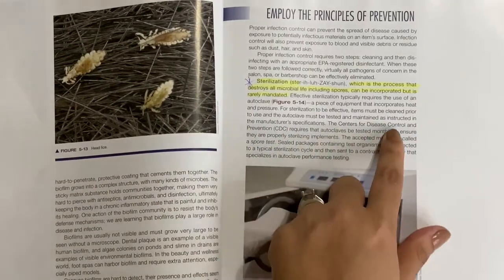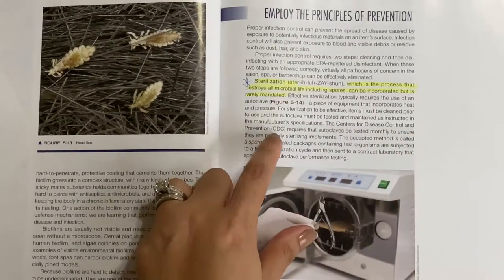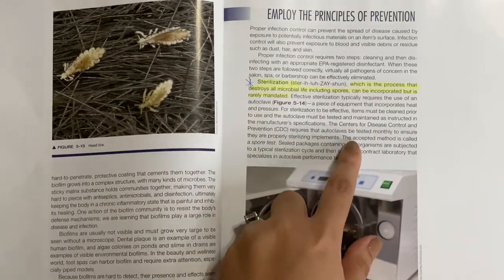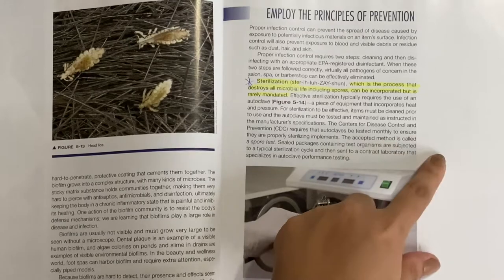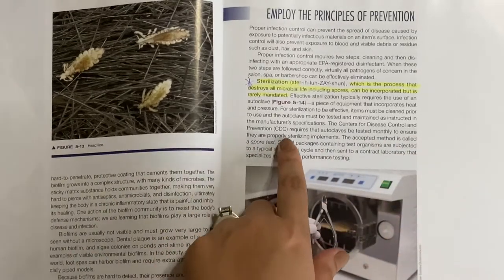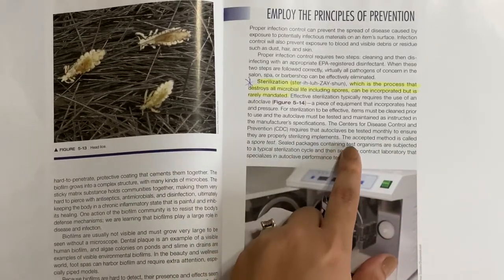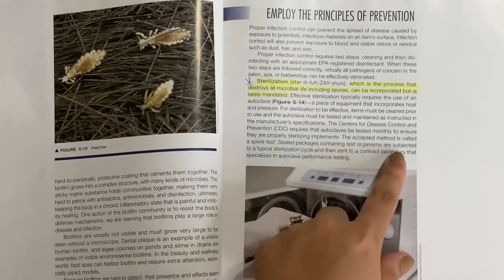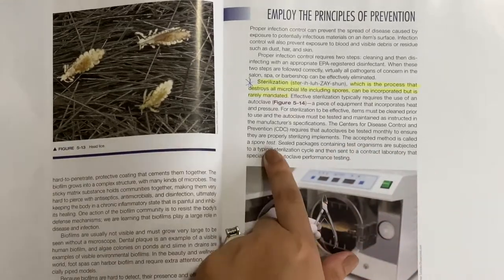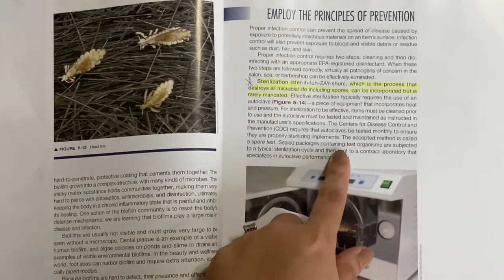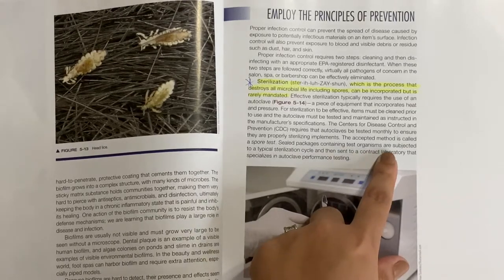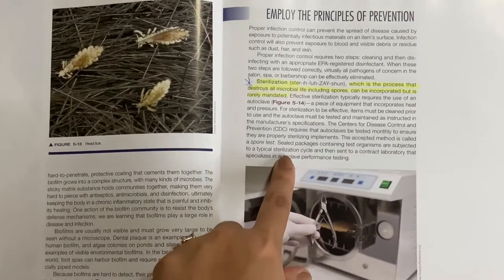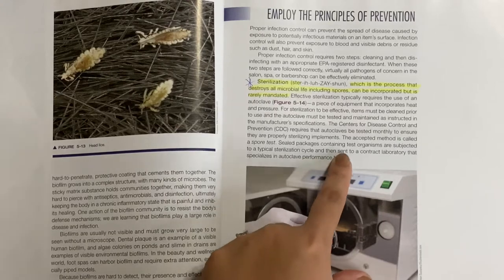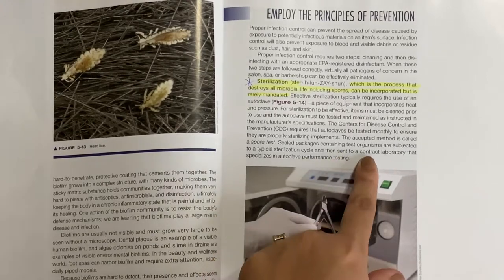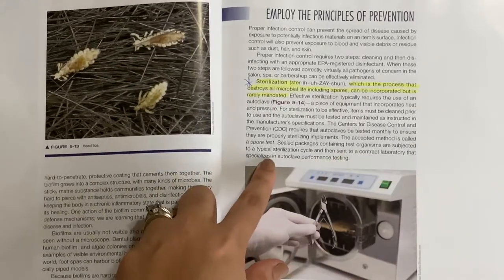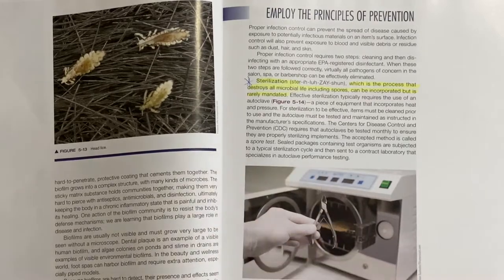The Centers for Disease Control and Prevention, CDC, requires that autoclaves be tested monthly to ensure that they're properly sterilizing implements. The accepted method is called a spore test. Sealed packages containing test organisms are subject to a typical sterilization cycle and then sent to a contract laboratory that specializes in autoclave performance testing.